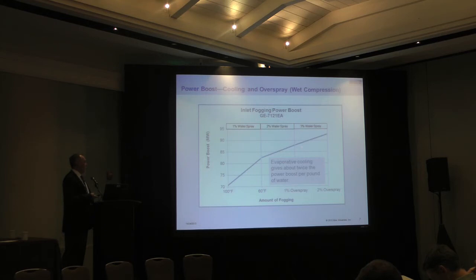And that gives us an additional power boost of about 5 megawatts in this case. So this was 12 megawatts for cooling for 1%. But for 1% of overspray, it's only about 5 megawatts. So the boost from evaporative cooling per pound of water is much bigger than from overspray fogging. But of course, the advantage of overspray fogging is if you do enough of it, you can get all the way from 70 to 93 megawatts, which is quite a large boost.